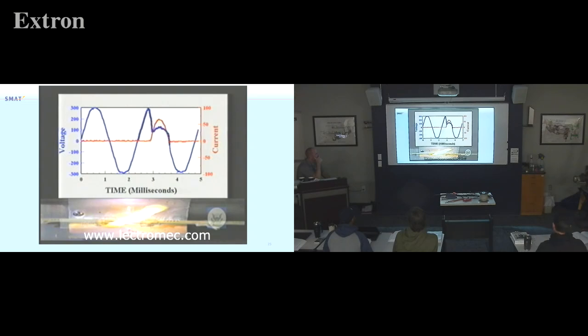However, the next cycle shows that the waveform has become distorted and that the voltage has collapsed into the waveform of a classic arcing event. The voltage then returns to its normal waveform as the arcing does not continue. The red line representing the current in the wire shows that to the left there is little to no current. However, during the arcing event, the current rises to a peak of 65 amperes.